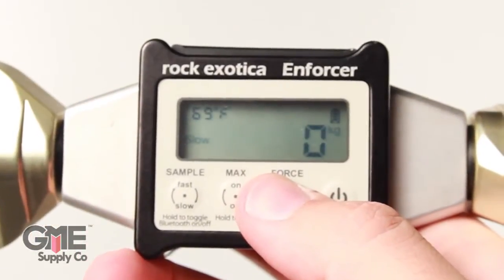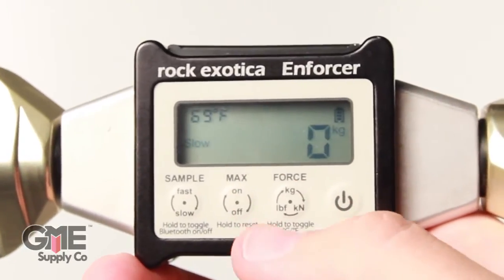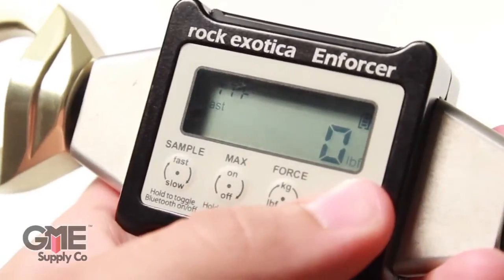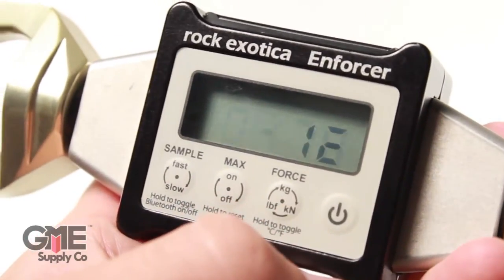The force button changes between force units. Each press cycles through kilonewtons, kilograms, and pounds-force. Holding down the force button changes the temperature setting between centigrade and Fahrenheit. The power button turns the device on and off — just hold the button for a couple of seconds. Battery level can be monitored in the top right.